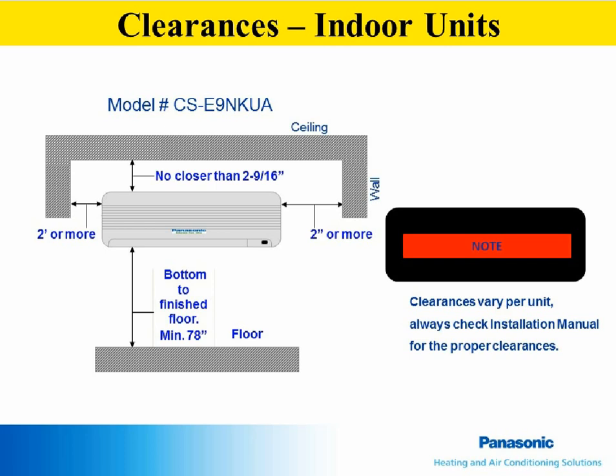This can easily happen in installations like the knee wall of a sunroom. If the unit is installed too high, like on a cathedral ceiling wall, the warm air might not reach floor level. Air throws are available in the service manuals of each model.